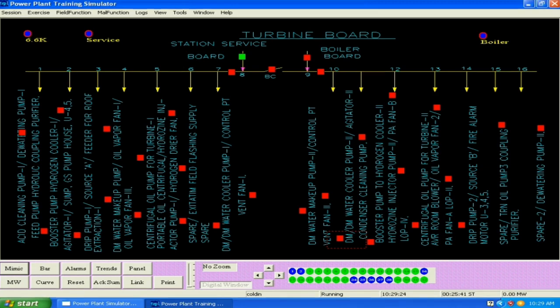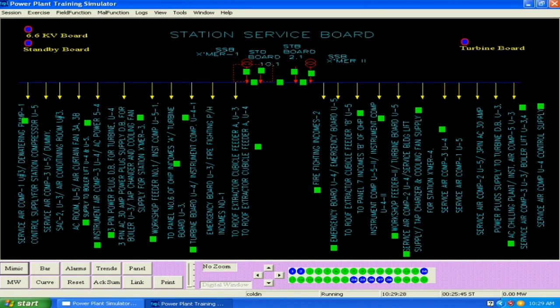Now we go to the station. After this, we go to the station service board. So on the station service board, we see that the supplies are not being extended up to the station service board. So we observe the mimic, and we go to E field page number 2 and 3, and make the supply on.